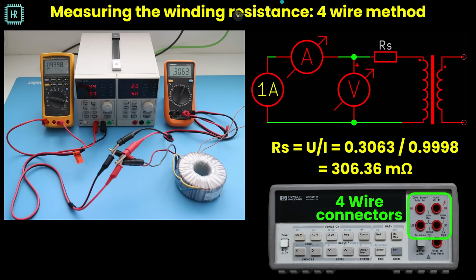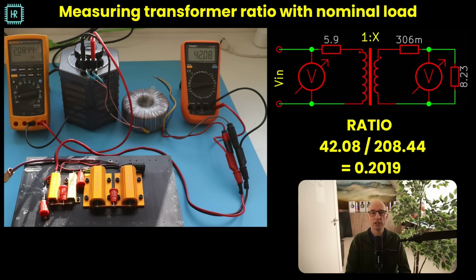You can use the same setup to measure the transformer ratio, but now with a load attached to it. This load resistor has a value of 8.23 ohms. The primary voltage is set in such a way that the secondary current is 5.1 amps, which is the nominal output current for this transformer.